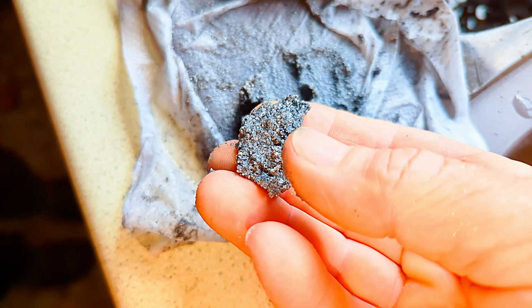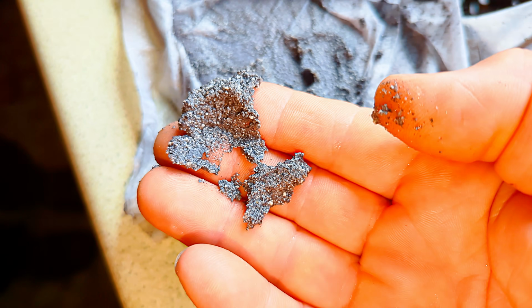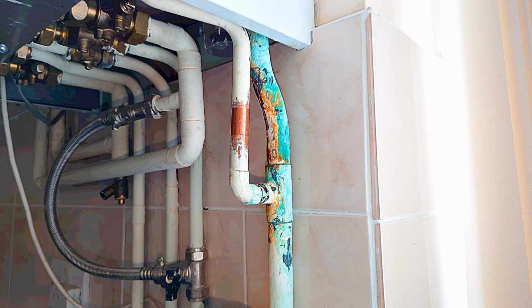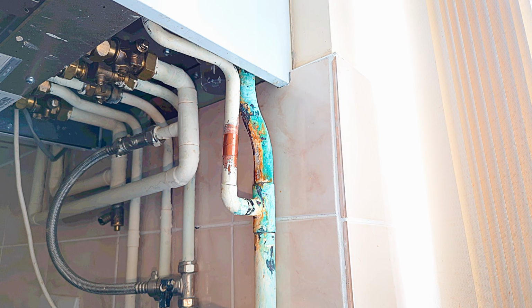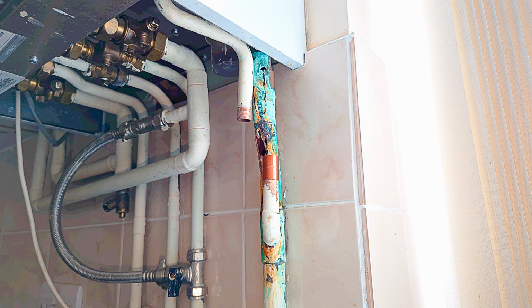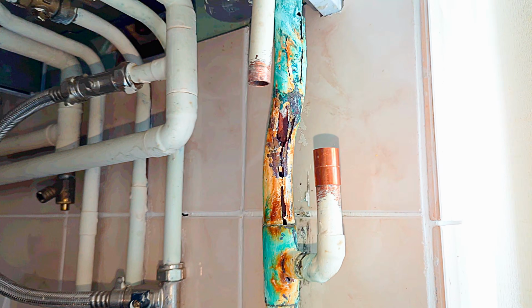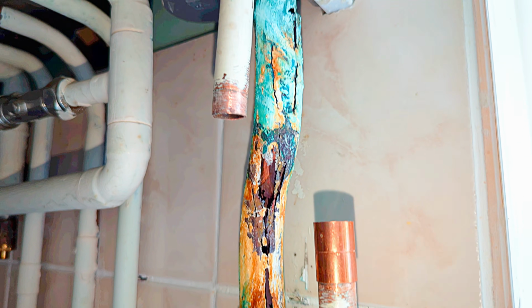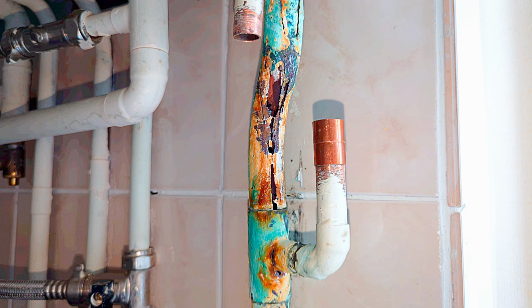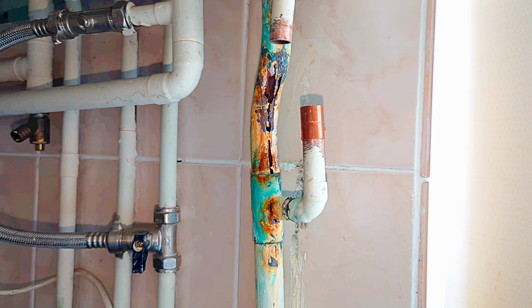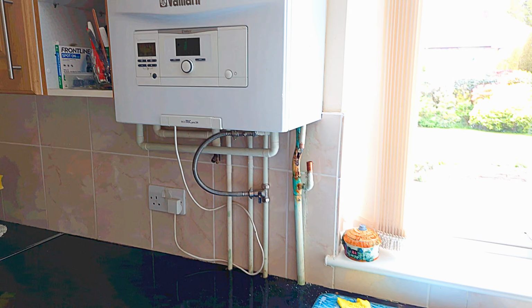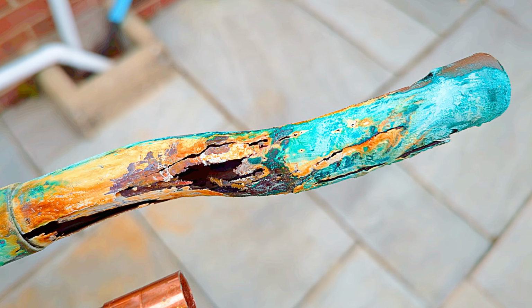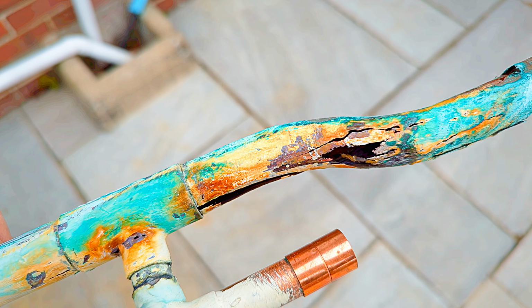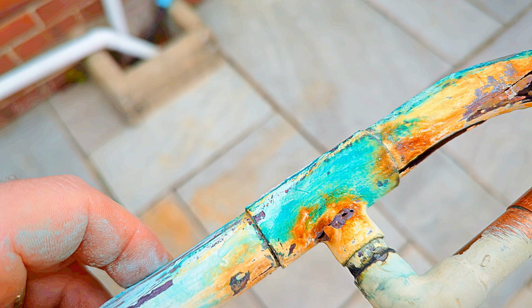Another interesting fact about this condensed water, it is extremely acidic, having a pH value of somewhere between 2 and 4. And this acidic water eats away at the aluminium heat exchangers, creating that aluminium oxide. It will also eat away at other metal materials and the lime which is in cement. And look what this condensed water has done to this copper pipe. It's completely eaten it away in just a couple of years. And that's why the pipes which are used to carry the condensed water should be made of plastic.